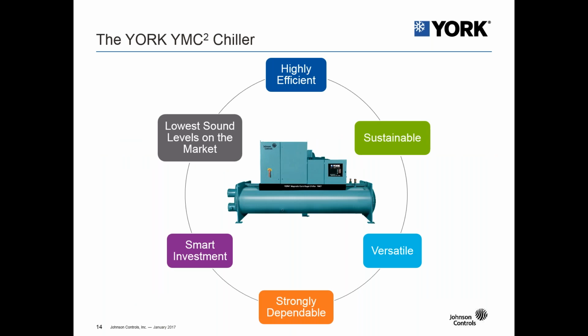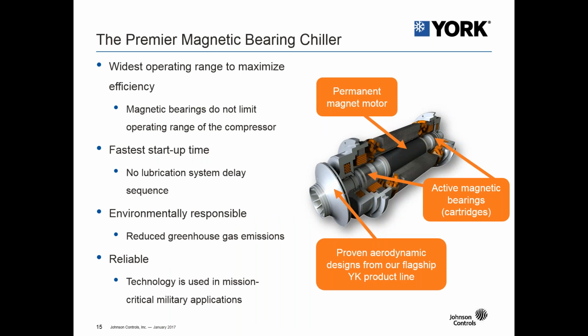So moving away from the bearings and taking a look from the total system layout of why it's important to look at it from a chiller standpoint, we'll see how the mag bearings truly provide an advantage in a chiller system. So on the right-hand side, you'll see a schematic of the York YMC² drive line. And the York YMC² utilizes a permanent magnet motor with active magnetic bearings. And you can just see a cutaway of the centrifugal impeller there as well.